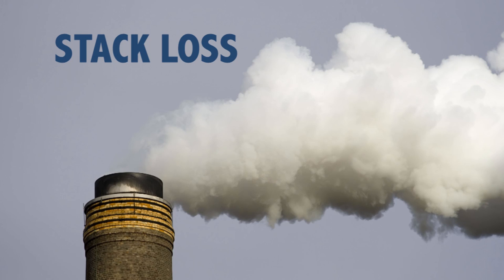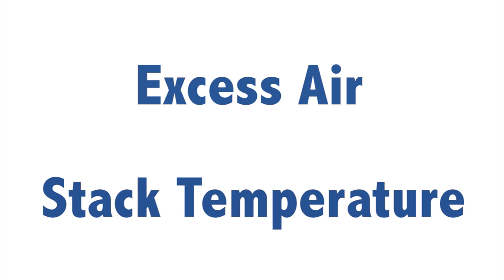The first loss is the stack loss. Stack loss happens because of high temperature flue gases leaving the stack, carrying away a lot of heat energy with them. There are two reasons for a high stack loss: one is excess air and one is the temperature of the flue gases itself. These two things combine to form the stack loss.